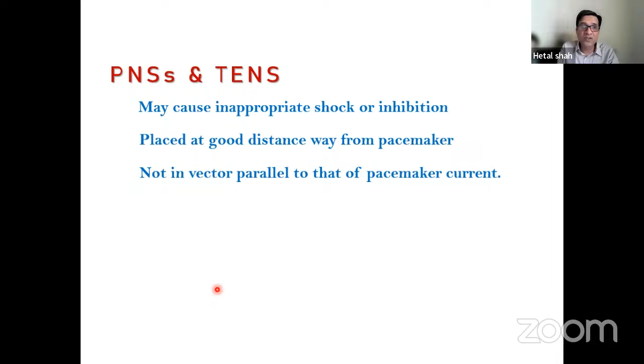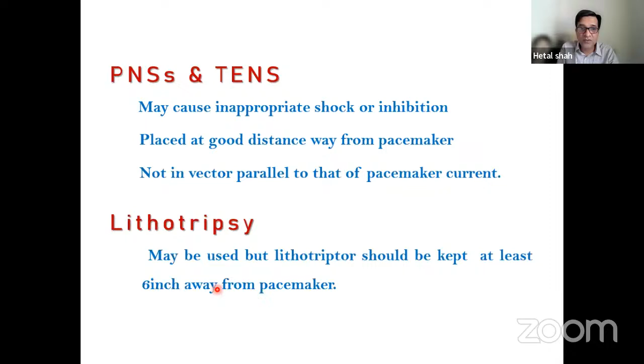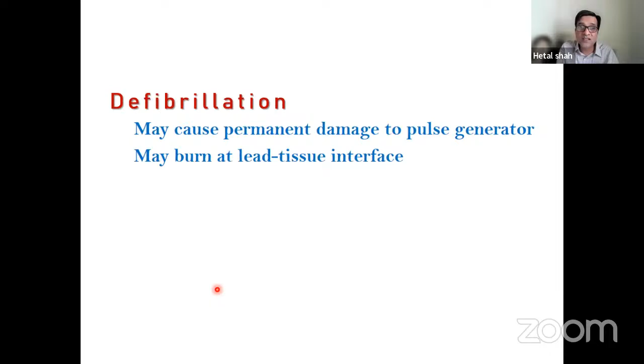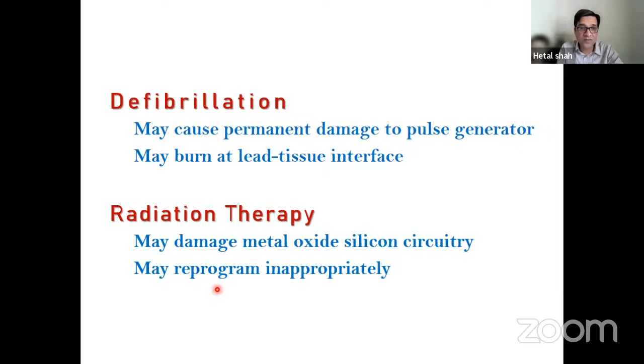PNS and TENS should be used very sparingly, or at a good distance from the pacemaker. Lithotripsy can be used, but it should be kept at least 6 inches away from the pacemaker. Defibrillation: if you have to use external defibrillators because of arrhythmia and the pacemaker or ICD is not working, then this defibrillation can cause permanent damage to the pulse generator, and it needs to be readjusted accordingly. Radiation therapy can also reprogram the device inappropriately, so it should be used with great caution.